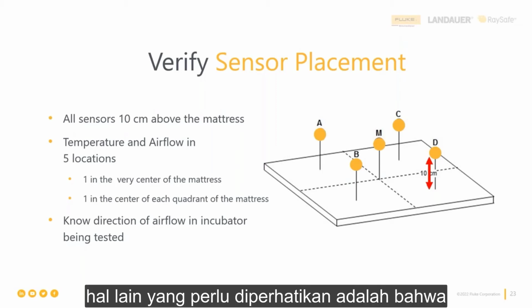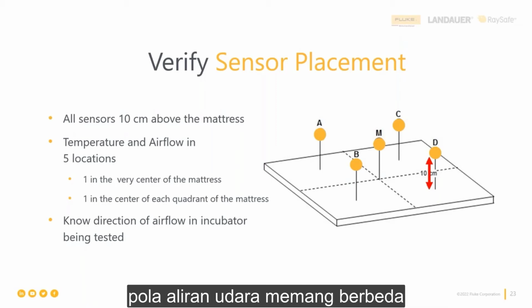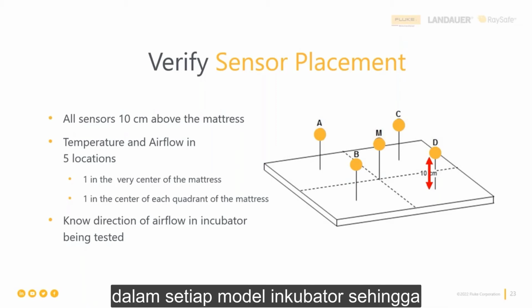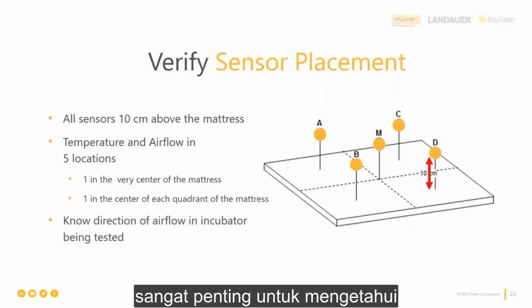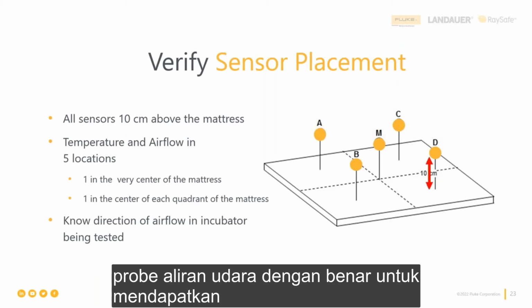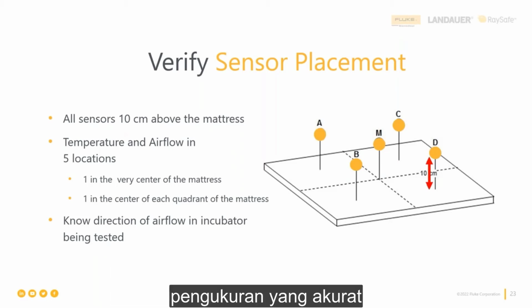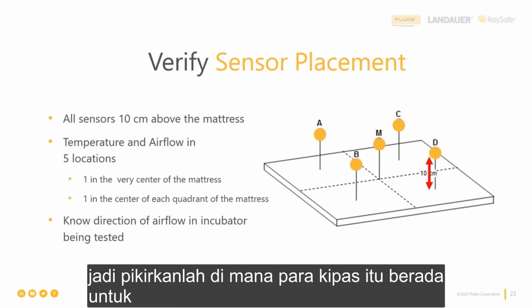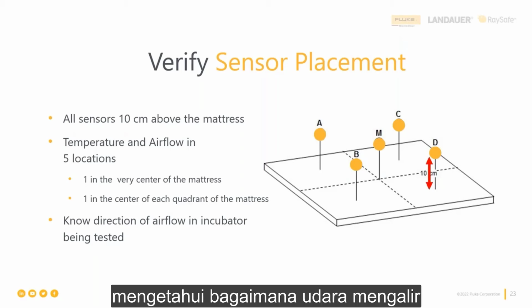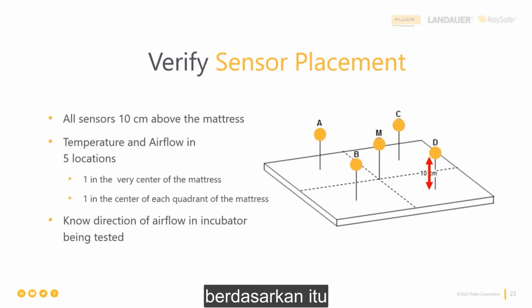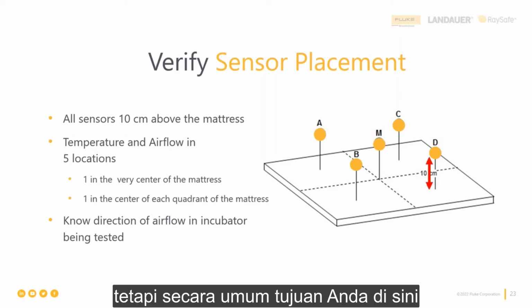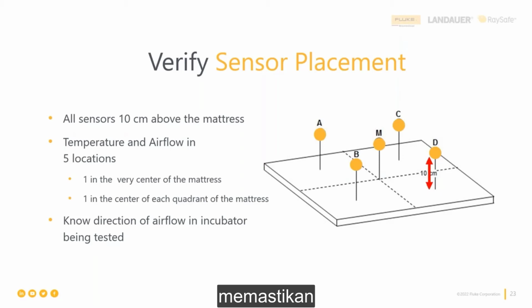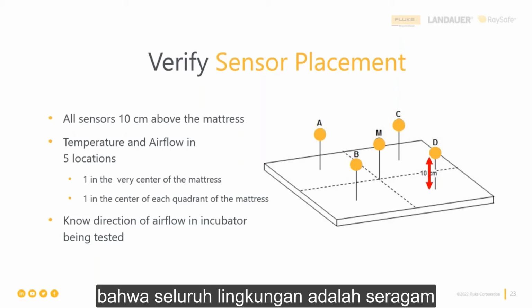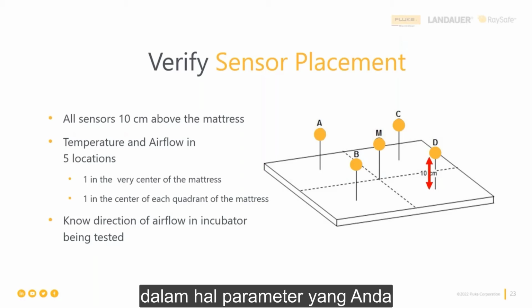And the other thing to note is that the pattern of airflow does differ in every model of incubator. So it is really important to be familiar with the direction of airflow inside the model of incubator you're testing, and make sure that you're placing the airflow probe properly to obtain an accurate measurement. So think about where those fans are, get a sense for how the air flows, and make minor adjustments based off of that. But in general, the goal here is to make sure that you're ensuring that the entire environment is uniform in terms of the parameters that you're testing.